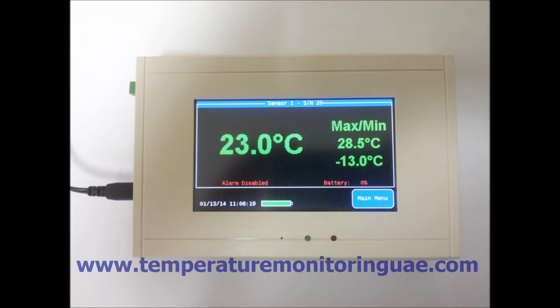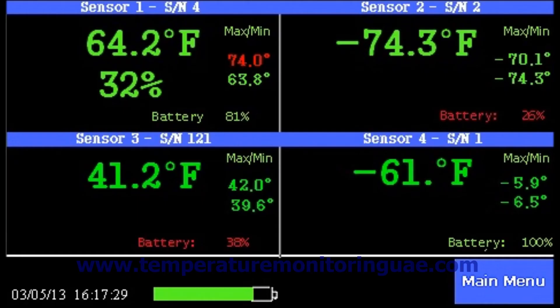Battery backup for power failure protection is provided by 3 AA type batteries which will operate the system for over 40 hours. In the event that power is not restored before the batteries are depleted, the stored data will still be retained although the data logger will not collect new data. The data logger is 21 CFR 11 compliant.